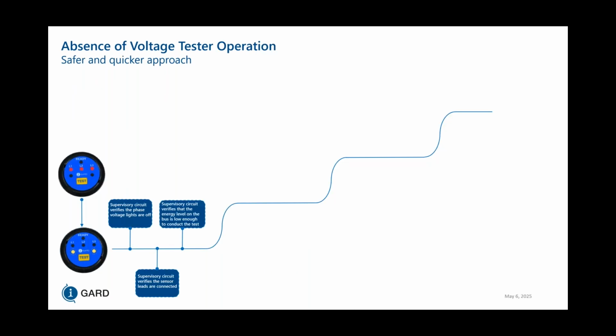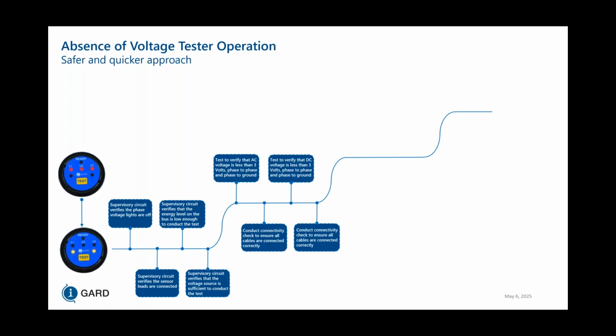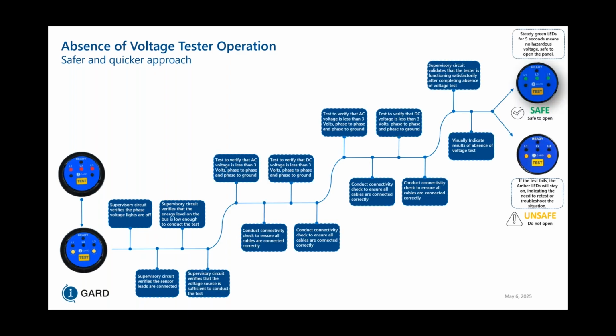So the test procedure for the absence of voltage tester is that it verifies the phase voltage lights are off, verifies the sensor leads are connected, verifies the energy level on the bus is low enough to conduct the test, and then verifies the voltage source is sufficient to conduct the test. Then it measures the AC voltage and DC voltage to confirm that it's less than 3 volts phase to phase and phase to ground. It checks that connectivity again, both in between the AC and DC test as well as after the DC test, and then it repeats that process once more on this stage here.